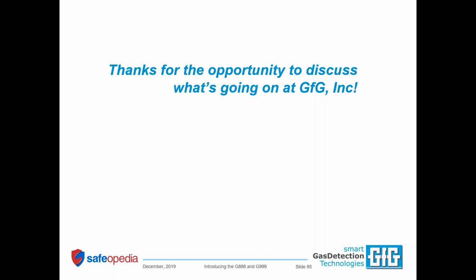Another question: can you alternate or change out various sensors? Yes, you can, but you're going to want to have that done by someone well trained by GfG, a technician rather than an unskilled person without a lot of experience with the instrument. The reason is, if you take the back off the instrument and look inside, it's a miracle of engineering, we pack a lot of stuff in there. As you disassemble it and remove and replace sensors, you want to do it with a little bit of TLC. So the answer is yes, but we're going to insist on a slightly higher level of training.